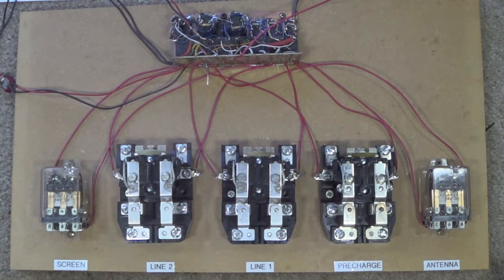When you go to switch the unit off, the action of turning the filaments off to the tube, that same switch activates the hold timer that allows the power supply to turn off, but it keeps the fan running and everything else live so that the tube can cool down for up to about 5 minutes, and then it just shuts off and everything goes dormant and quiet.